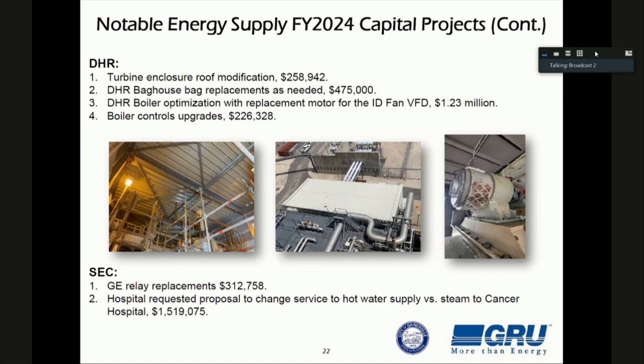Boiler optimization. So the chief operating officer mentioned, most of our fans run on a heavy motor, so they run full speed, and we control flow by dampers. So you basically have a fan running, and you're controlling it by controlling flow through it. A lot of electricity used. Variable frequency drives allow you to run the motor, and you vary the speed of the motor. So you're controlling the flow by the motor. Significantly smaller motors, significantly less electricity being used because you're not stifling it by controlling the output.